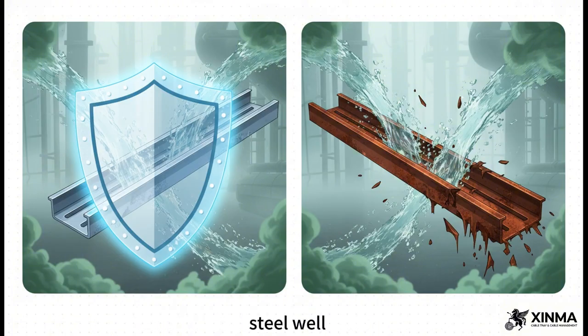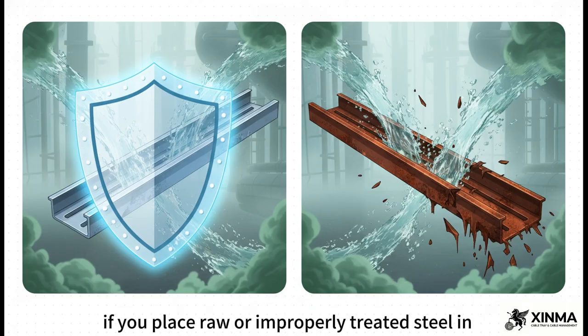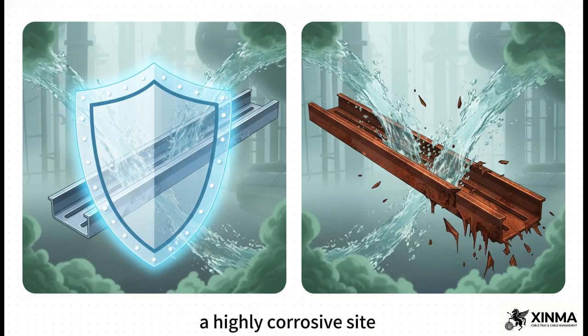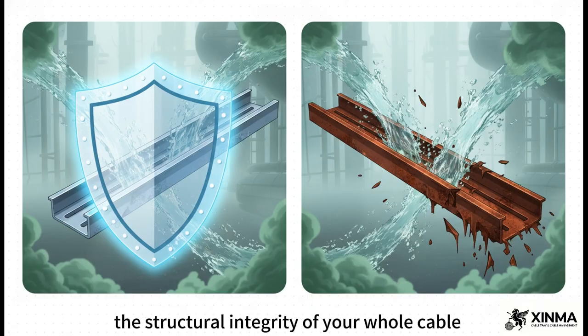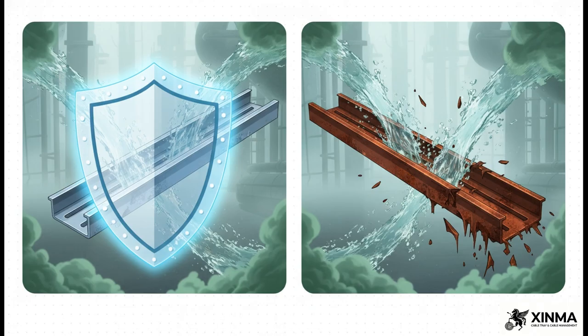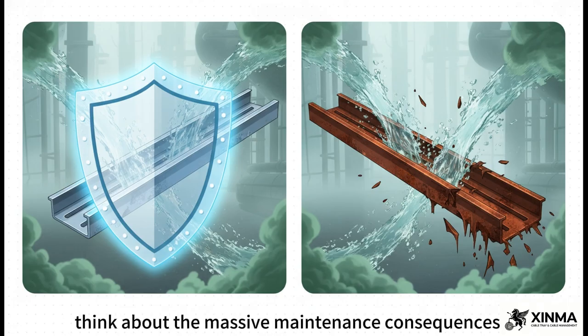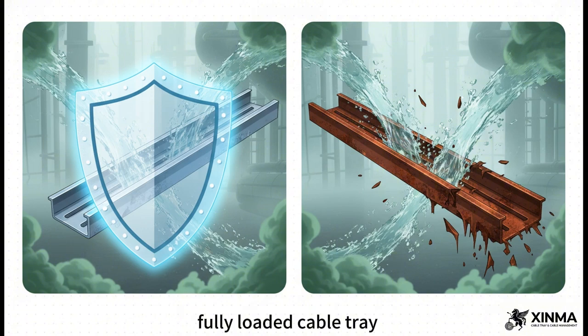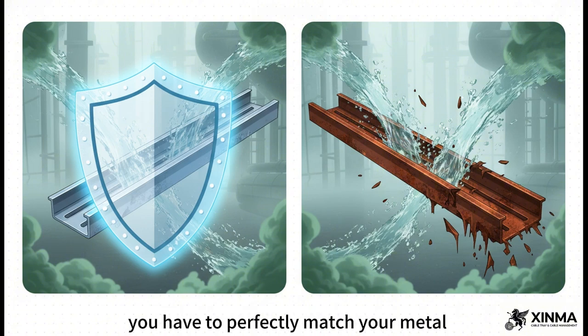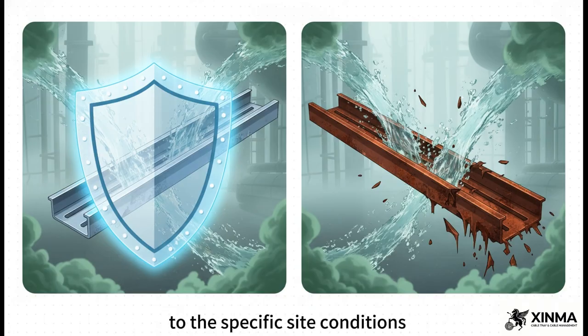But steel? If you place raw or improperly treated steel in a highly corrosive site, it is going to fail first, for sure. It'll rust, degrade, and rapidly compromise the structural integrity of your whole cable management system. Think about the massive maintenance consequences of replacing a failed, fully loaded cable tray years down the line. It's a total logistical nightmare. You have to perfectly match your metal to the specific site conditions.